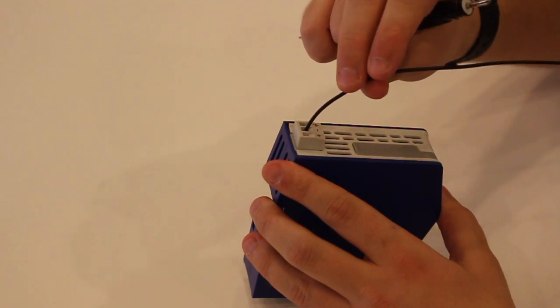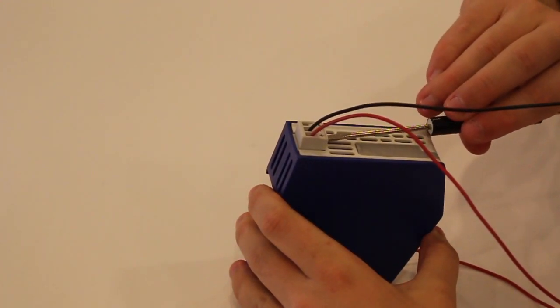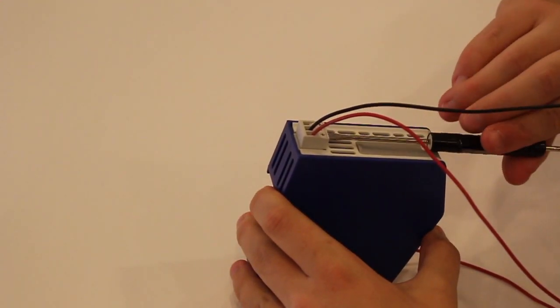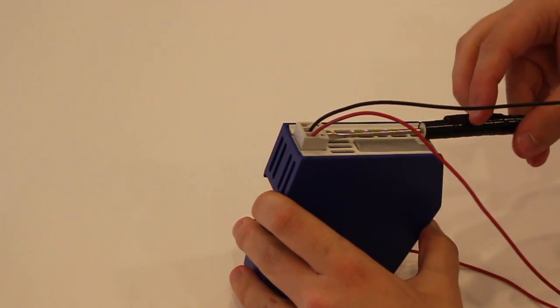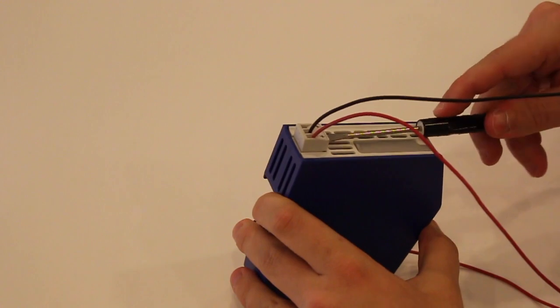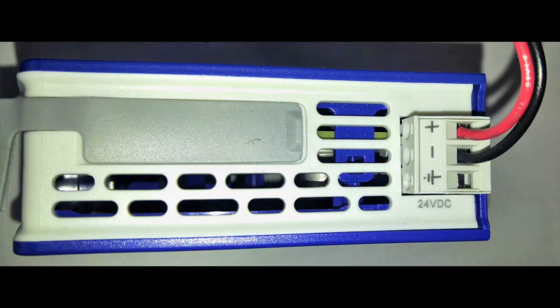We'll start by installing the power connector. To perform this part of the installation, you will need a small standard screwdriver. The BW4031 DC power supply requirements are 7 to 40 volts DC with the typical voltage being 24 volts DC. Locate the 3-position terminal block connector and connect the DC plus and DC minus wires to the connector.